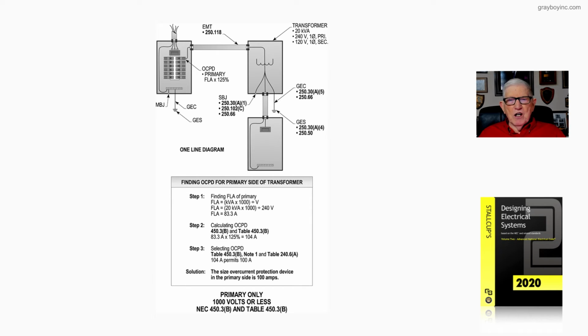But now, reviewing our Step 1 and the boxed-in information with the title heading, finding the overcurrent protection for the primary side of the transformer. Step 1, full load current equals kVA times 1,000 divided by the voltage. So you have a 20 kVA transformer times 1,000 divided by 240, 83.3. Now, notice in Step 2, we apply what 450.3(B) instructs us to do by using those percentages found in Table 450.3(B) based upon the transformer's primary current being over 9 amps, which is 83.3. So we can select 125% based upon this value. We come up with 104.